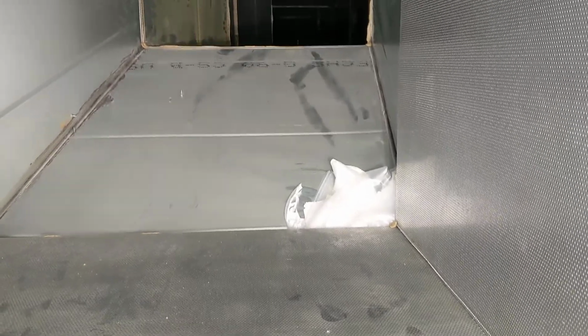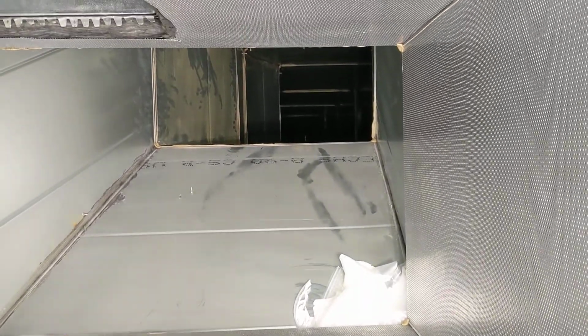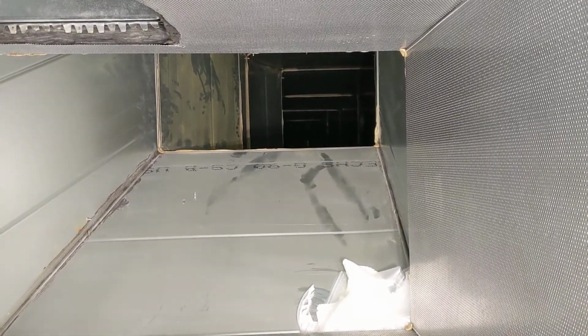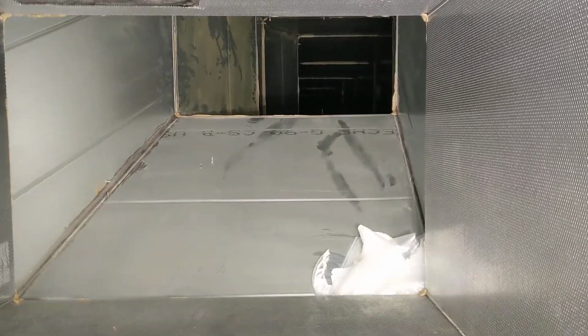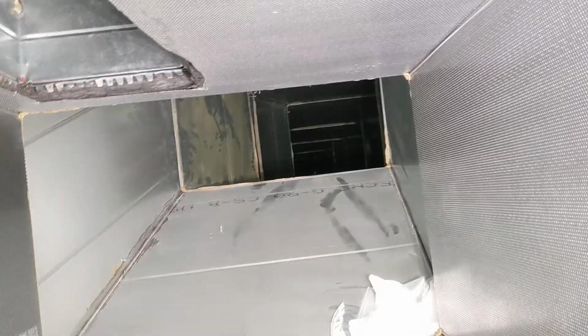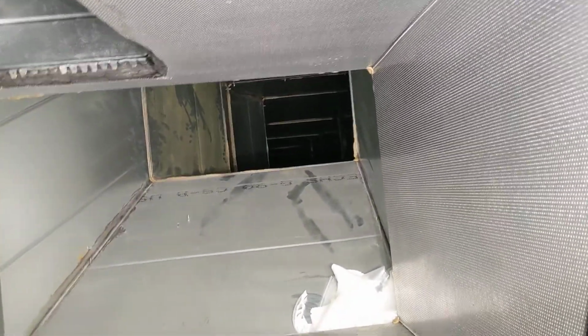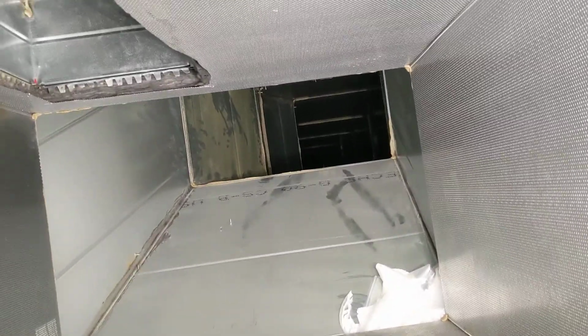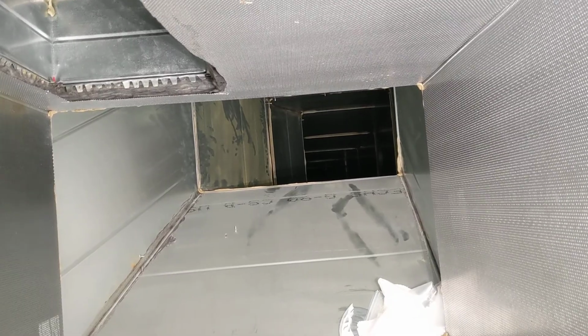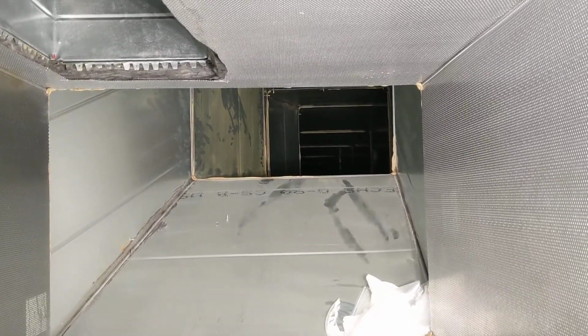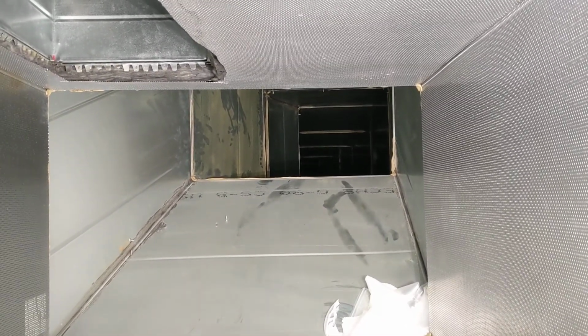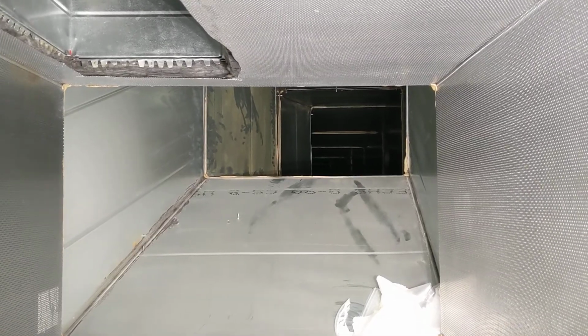You can see where I've already moved some dust and dirt out of the way just to show what clean is and what dirty looks like. You can see on the wall all that dust and dirt buildup. I have my HEPA vacuum with me, so I'm going to go all the way down to the end and HEPA vacuum my way back, down every branch I can fit down that my other guys on the ground outside the ductwork haven't already whipped.